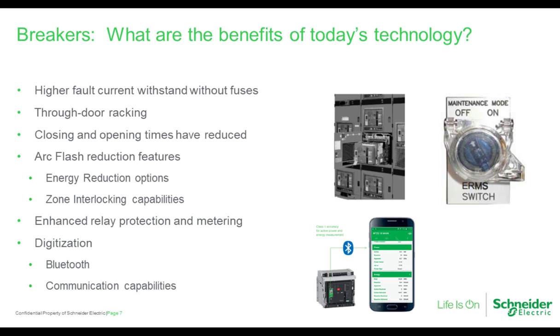Enhanced relay protection and metering. Digitization of the trip units with Bluetooth, communications capability, touch remote. These offer the ability to step away from the breaker while operating. And it also is a point where more information can be provided to the operator.